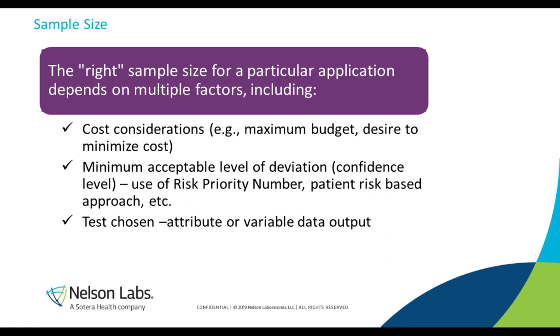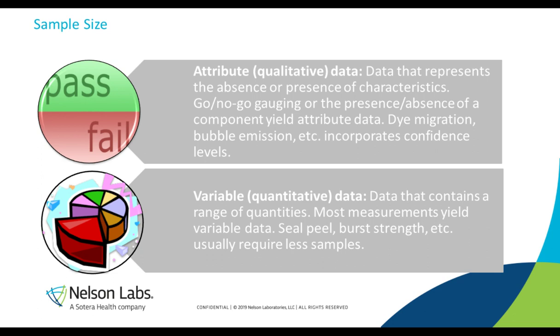Additionally, the test that you're going to be using will drive a test sample size. Attributes are going to have a lot higher sample size than variables, and that's because they're usually a go or fail test. Let's look at that a little bit more. So when you're looking at attribute data, you're getting a pass-fail or a go-no-go type of a result. Dye migration and bubble emission are these types. So you might consider having higher sample sizes for these types of results, whereas when you're doing seal peel or burst, you're getting an actual data point that you can compare to a range.